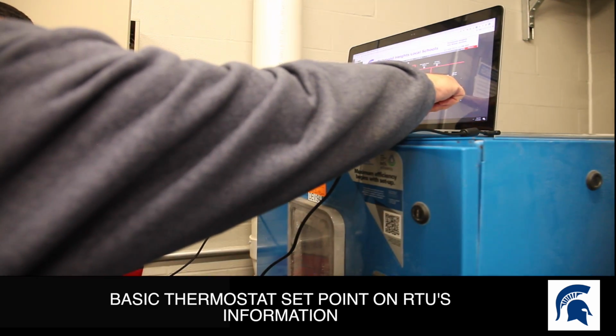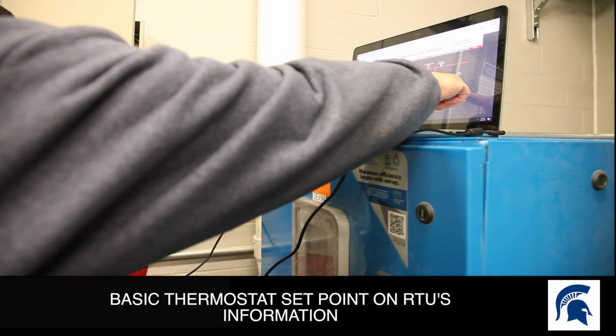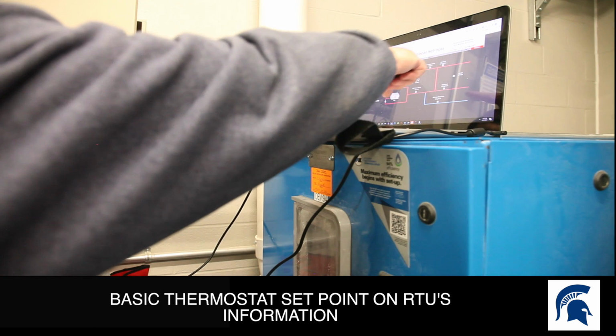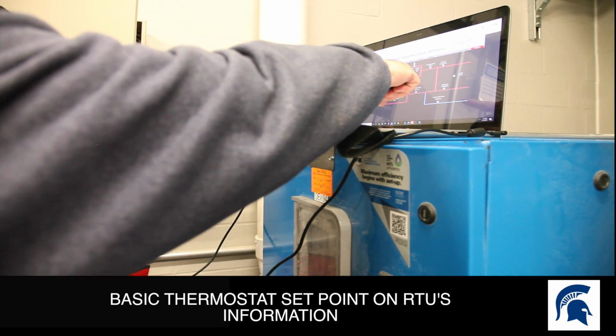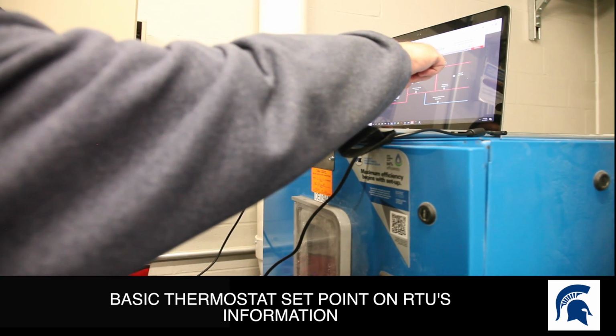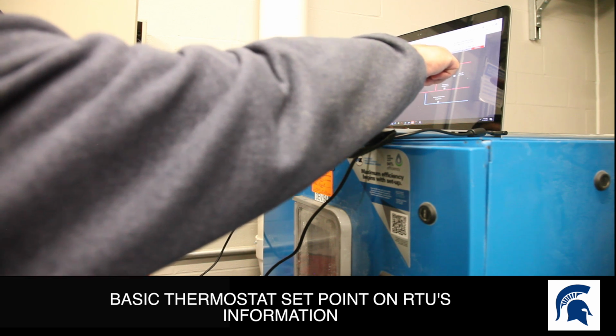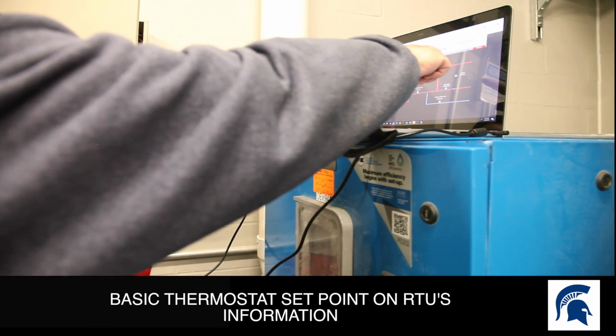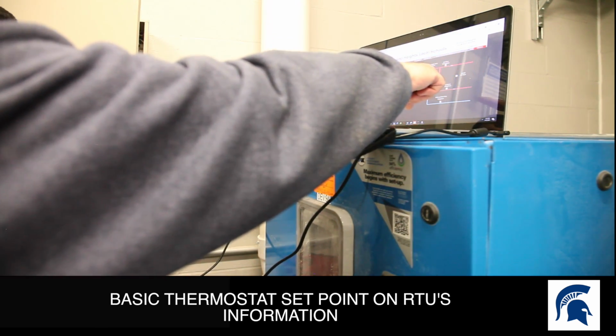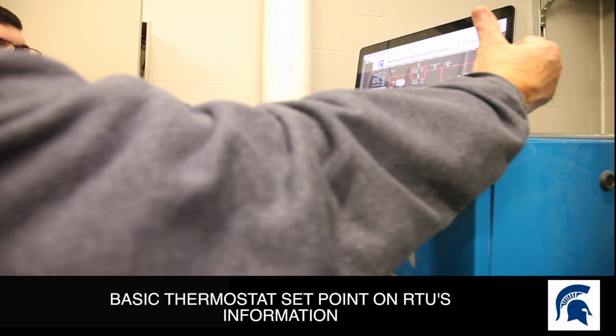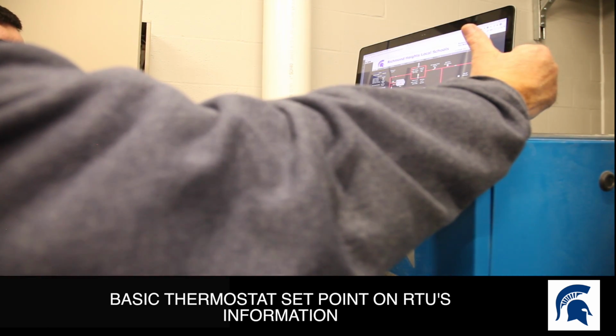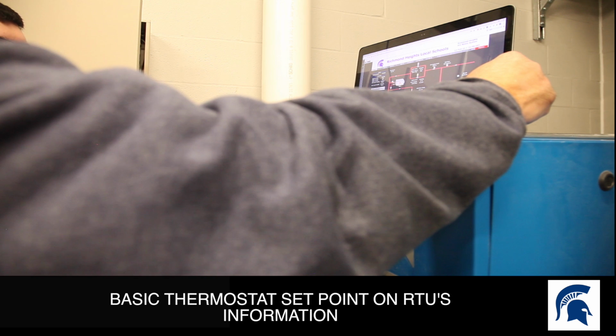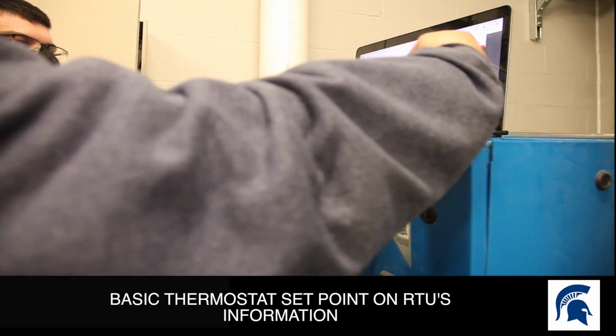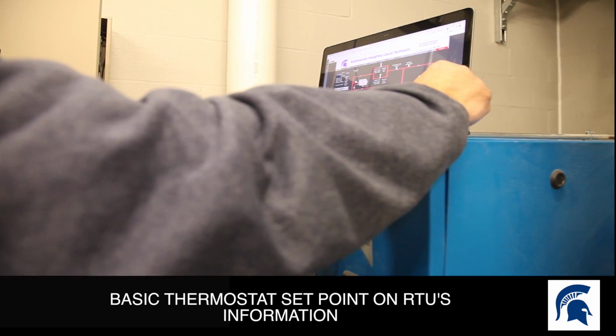Hot water return, what does that say? Gallons per minute. So 72 gallons a minute. The temperature's 121.4. The water flow going out is 104. So why is it flowing out faster than it's coming back in? Because they're working on the pumps? Yeah, that's the only thing I can think of that would cause that. Those should be close to the same. Yeah, close to the same, I would imagine.